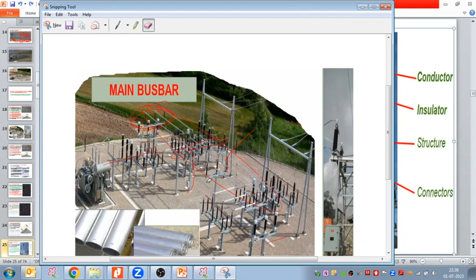So this is the rigid bus bar support and the rigid bus bar height, and for each bay we provide this kind of support. And in case we have the double main bus bar, the main flexible bus bar arrangement, how do we do that? For that again, we take separate support structures, we make separate beam tower stringing, then we take the second bus bar, the third bus bar, again on a separate support structure, the tower and the gantry.